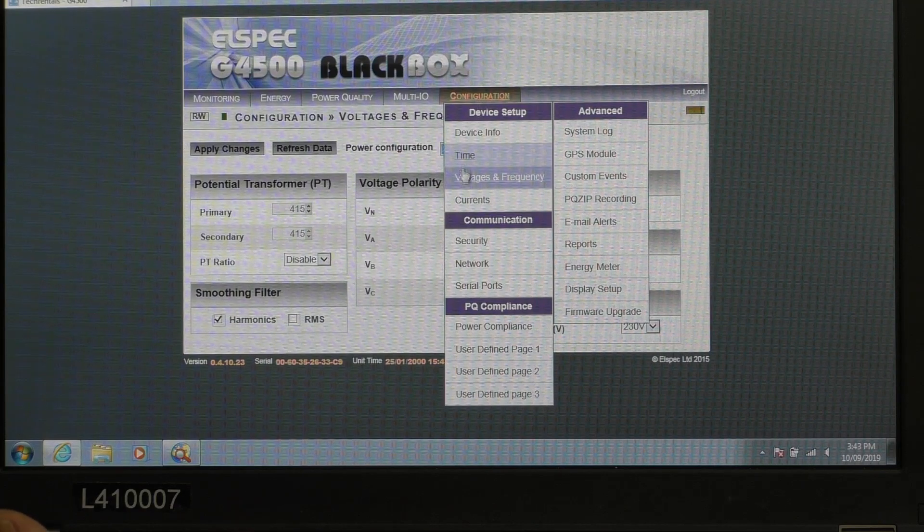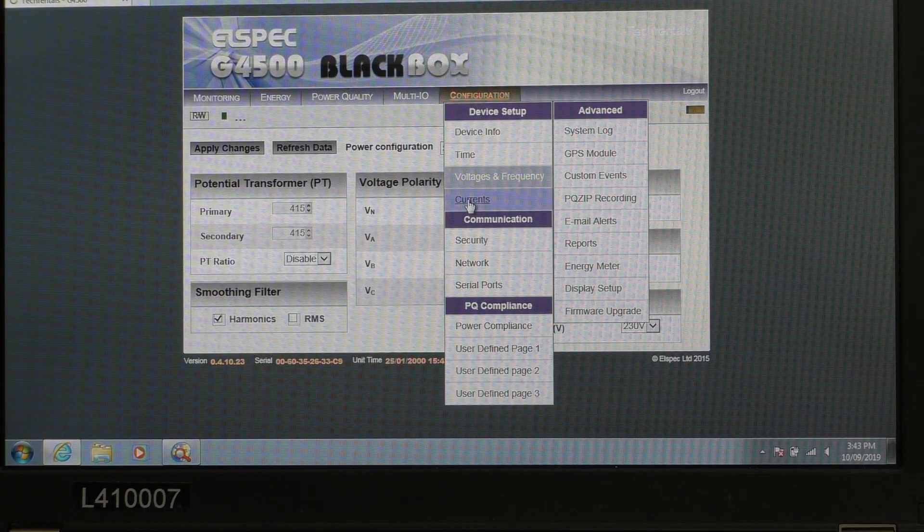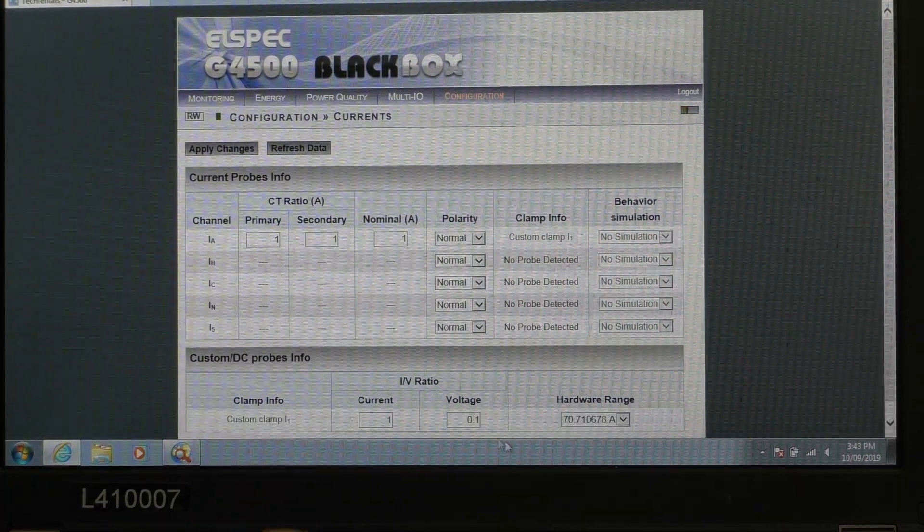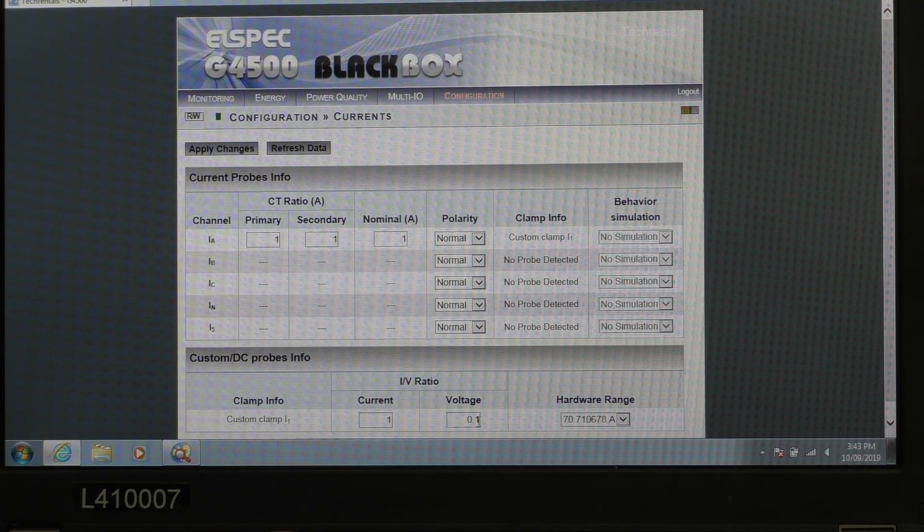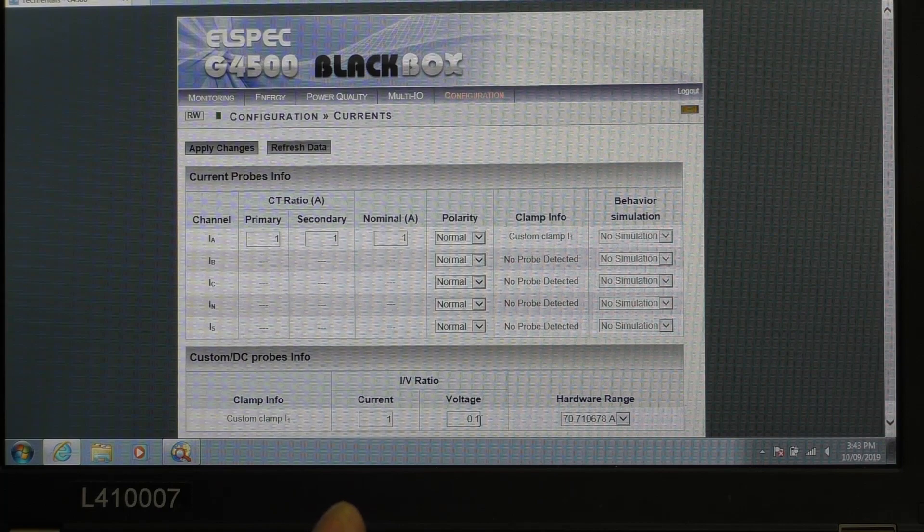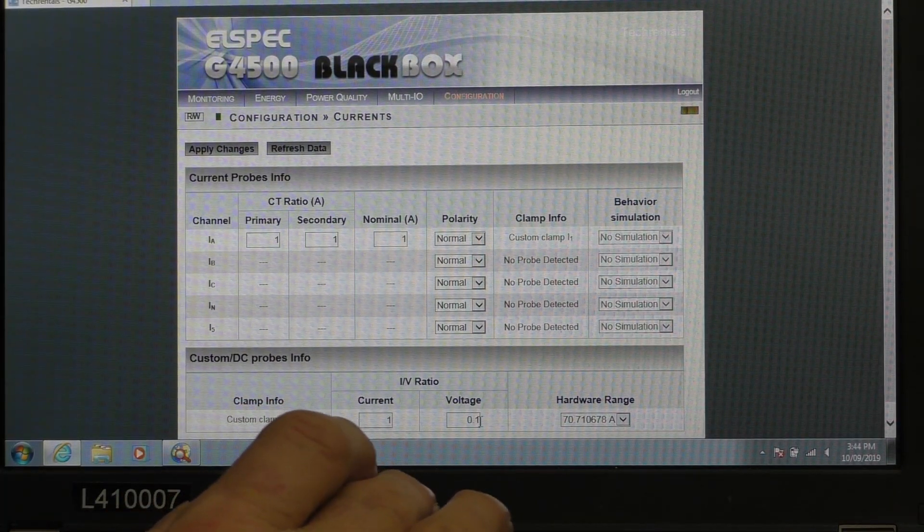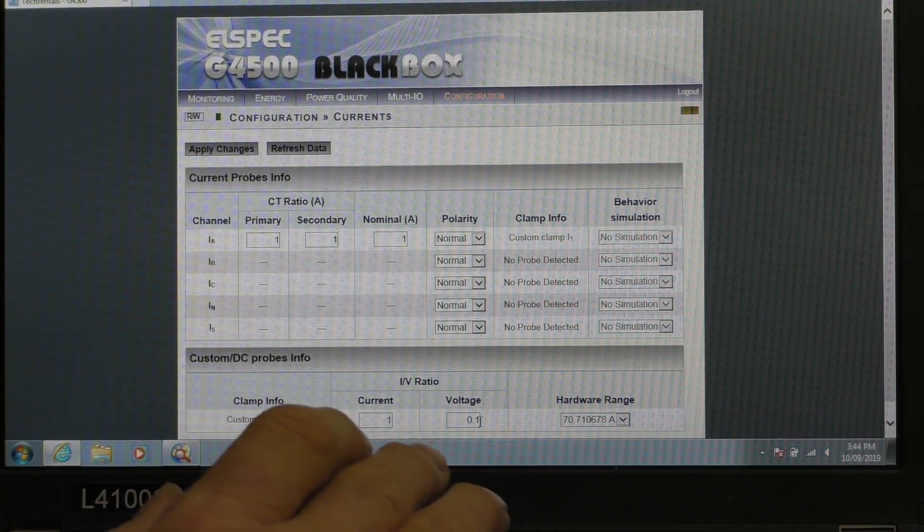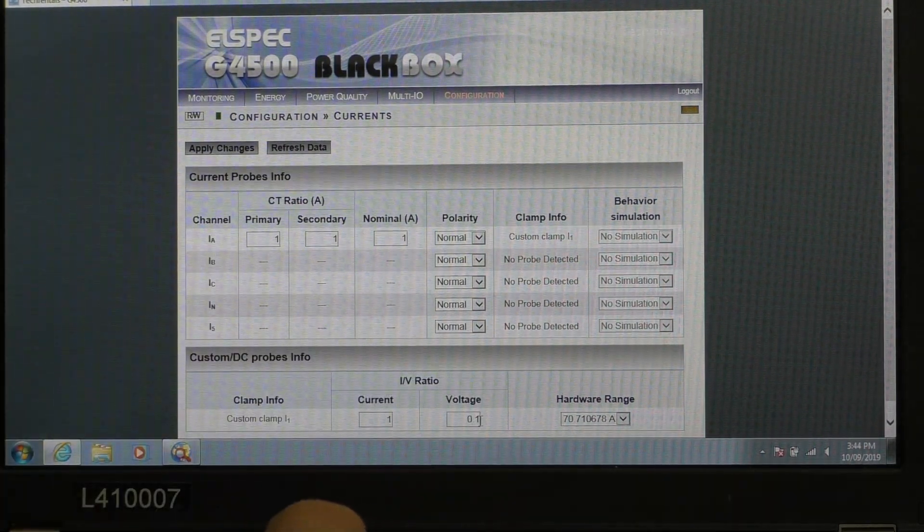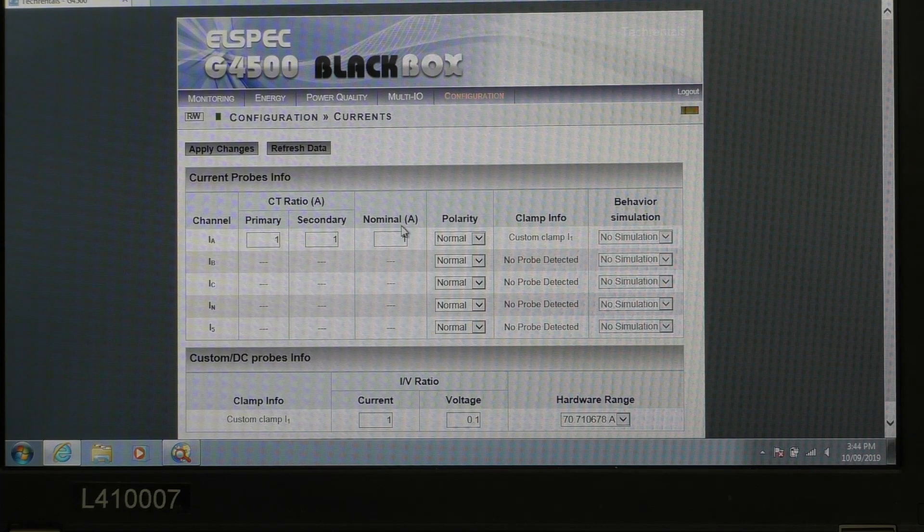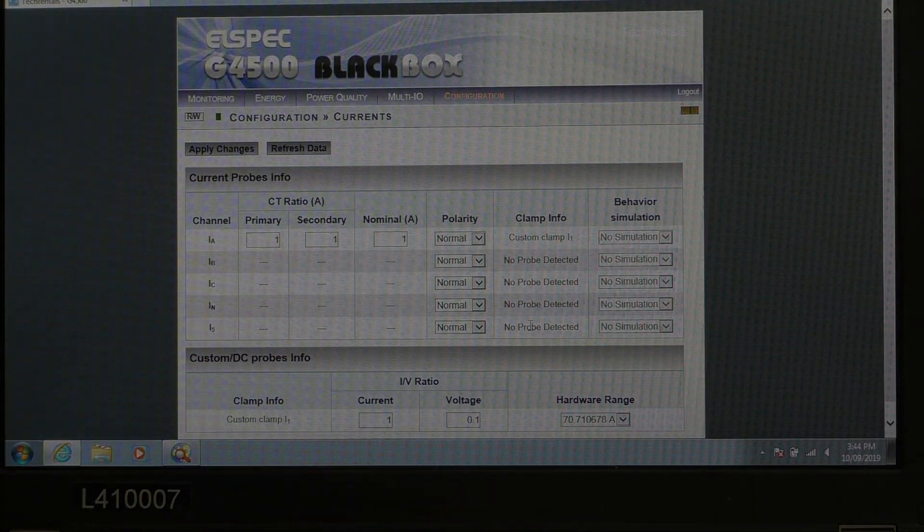Next thing under configuration, we've got to check we've got the right current clamps. Right. Now, current clamp we've set, this was the setting on the thing. The three settings, it'll either be 0.1, 0.01, or 0.001. The highest one is 0.1, and that's 100 millivolts per amp. So 100 millivolts per amp, which is correct. And otherwise we'd need to set those for the three. Okay.